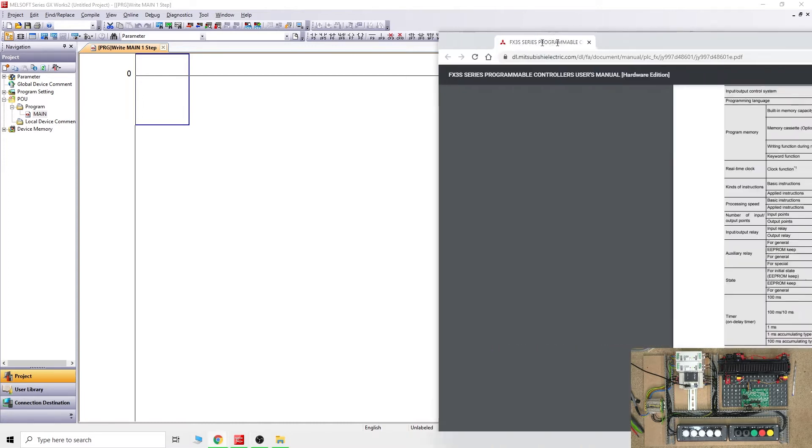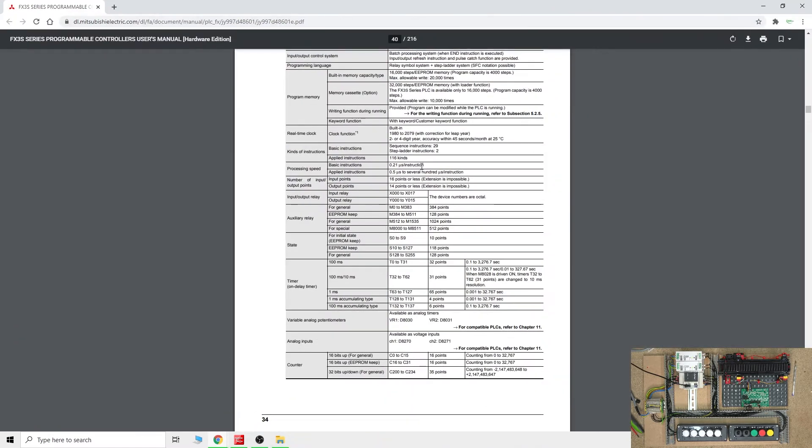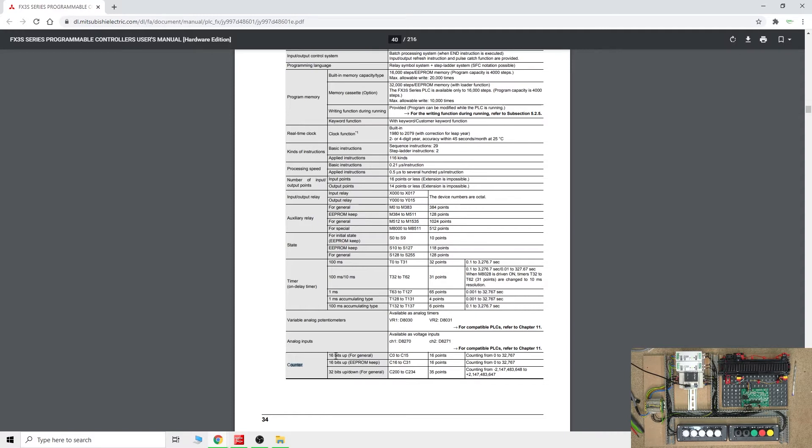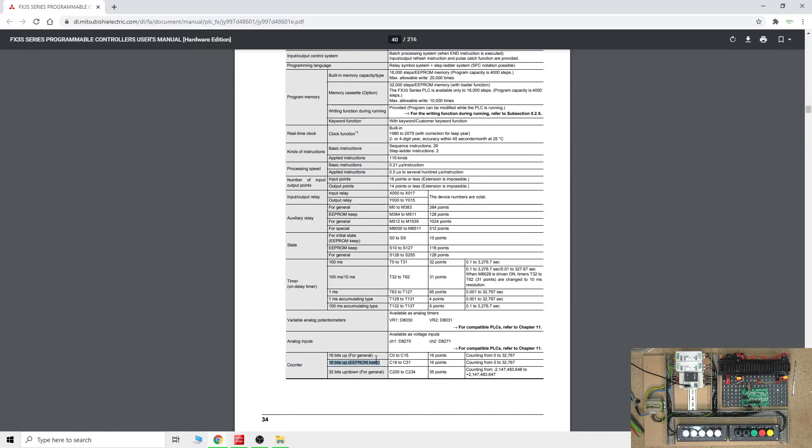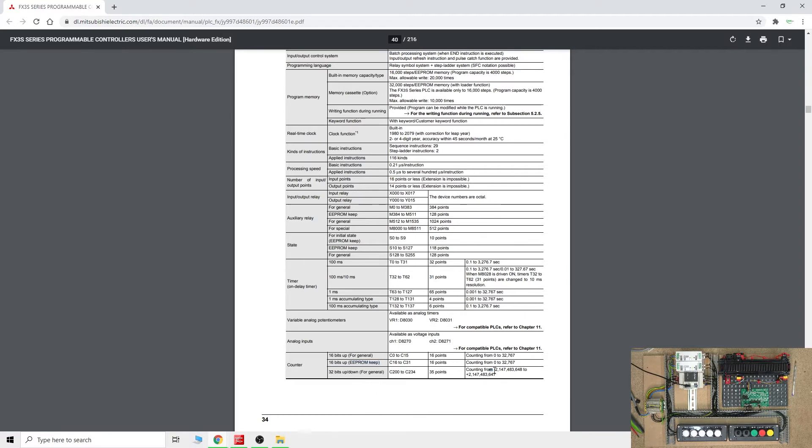Let's check what is available for our specific PLC. If we go down here, we can see the counter section. This PLC has 16-bit up counters from C0 to C15, then we got 16-bit counters for EEPROM keep. We also have C200 to C234, which are 32-bit up-down counters for general use.